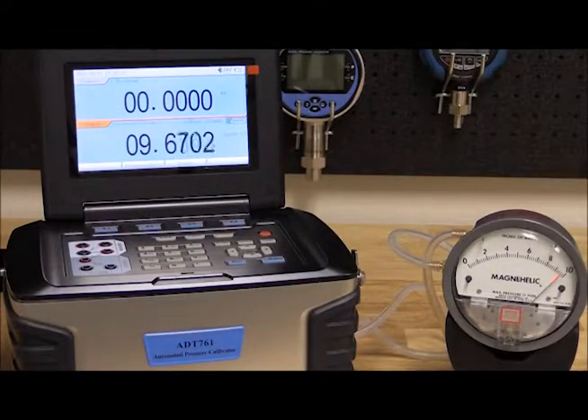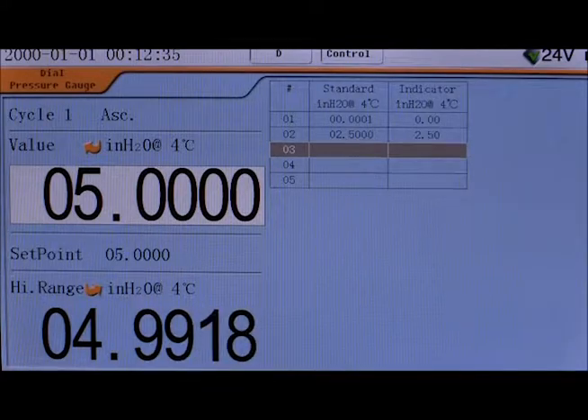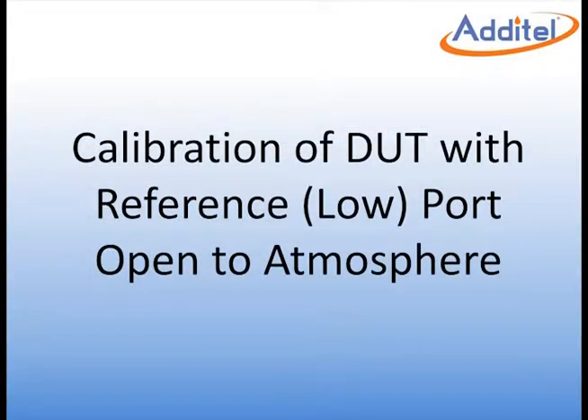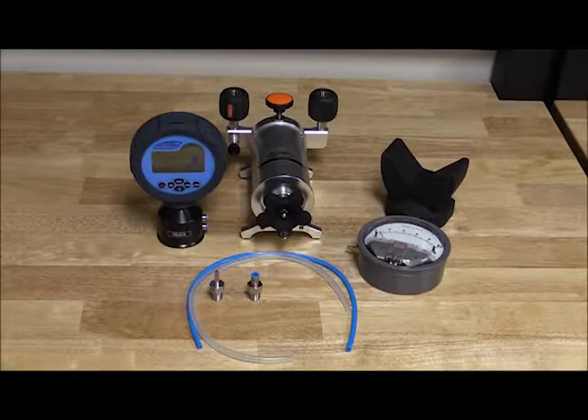In this video, we will demonstrate 3 different ways to calibrate a differential pressure gauge and the pros and cons of each method. In this example, we will use an Additel 901 pump to generate the pressure. The Additel 681 differential gauge will be used as our accurate reference, and we will be calibrating a Magnehelic differential gauge that is 0 to 10 inches of water.